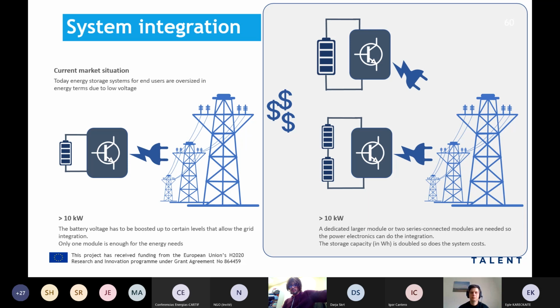You need a DC link, which normally is in the range of 700 to 800 volts. That means that in order to interface the battery, you need almost always, at least for this range of powers and energy, a DC-DC converter that is able to step up the voltage from the battery terminals to the DC link required, those 700 to 800 volts.